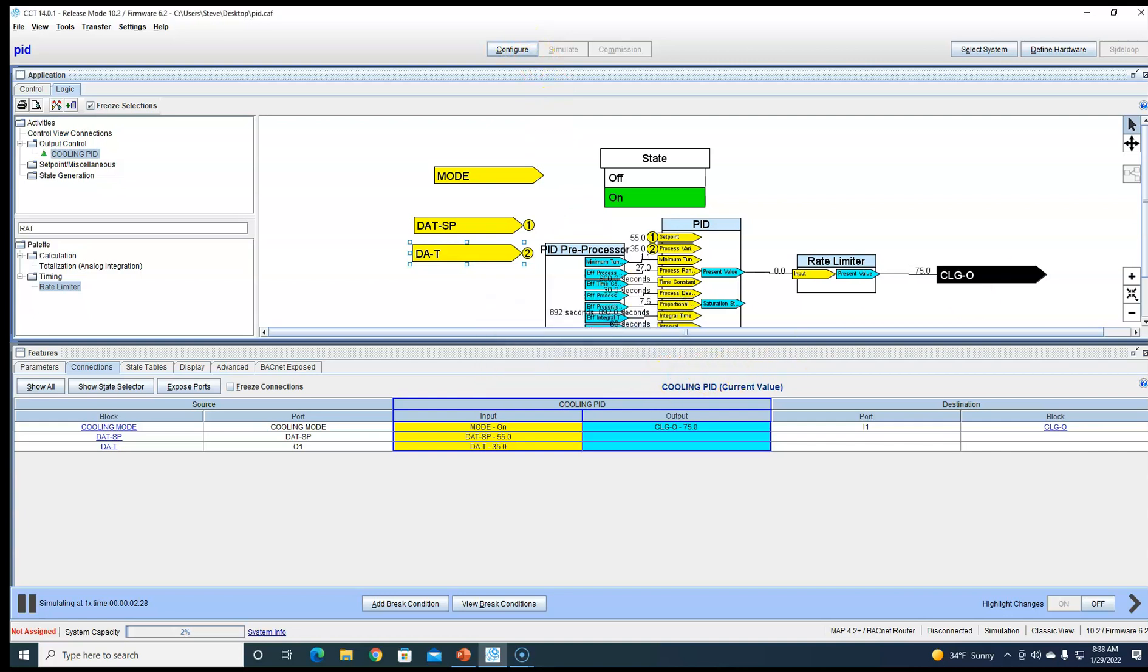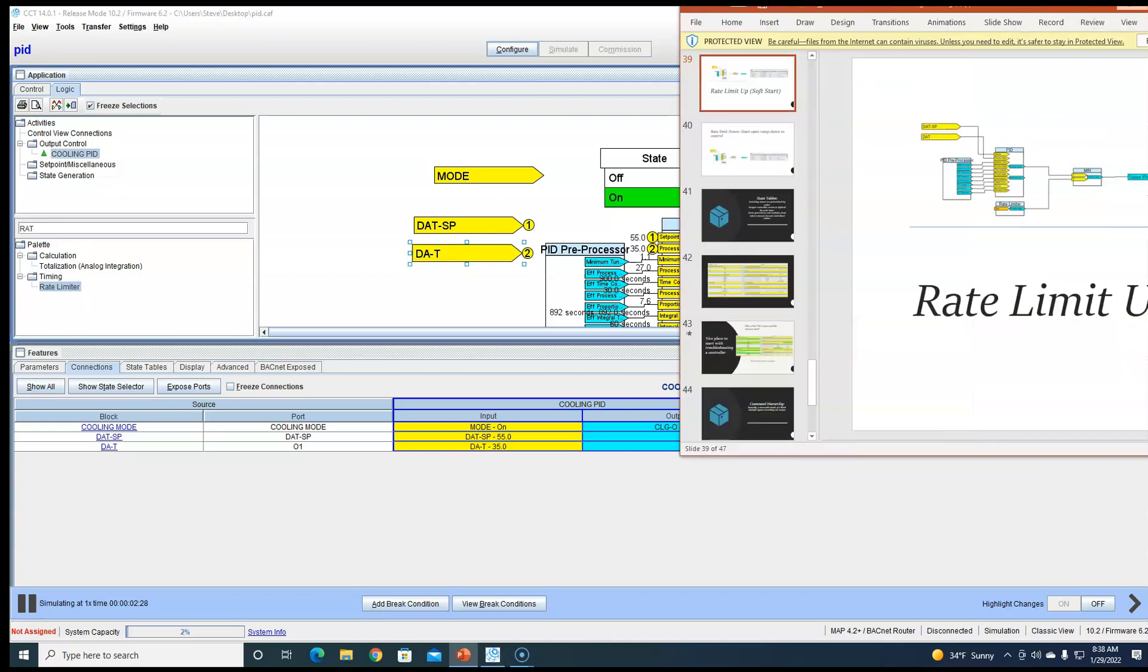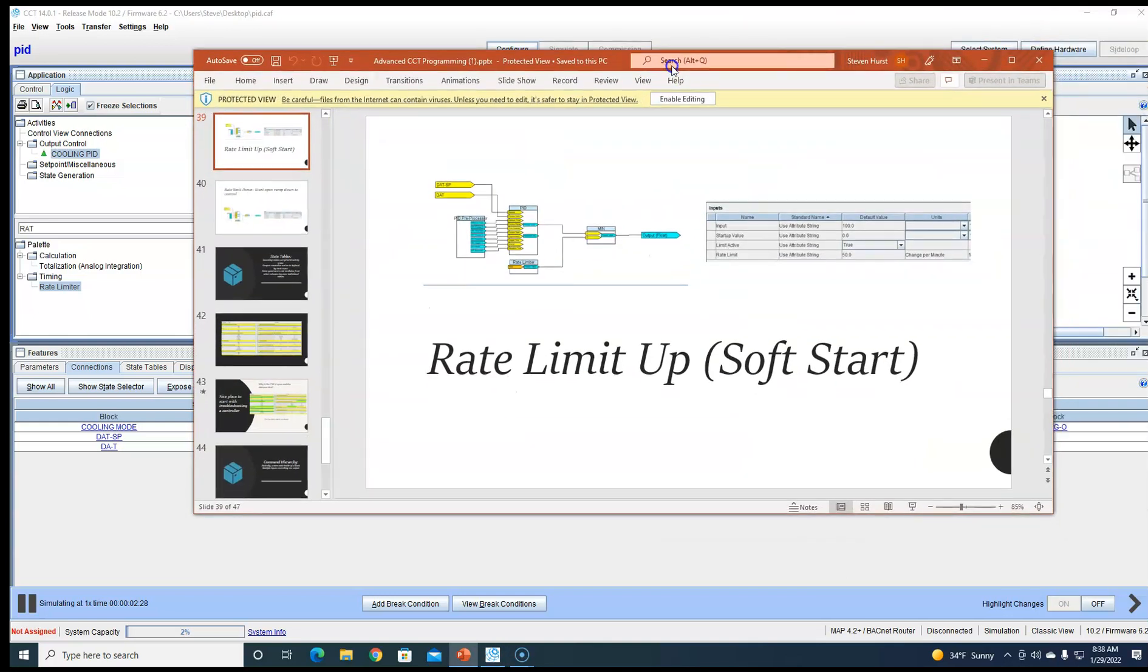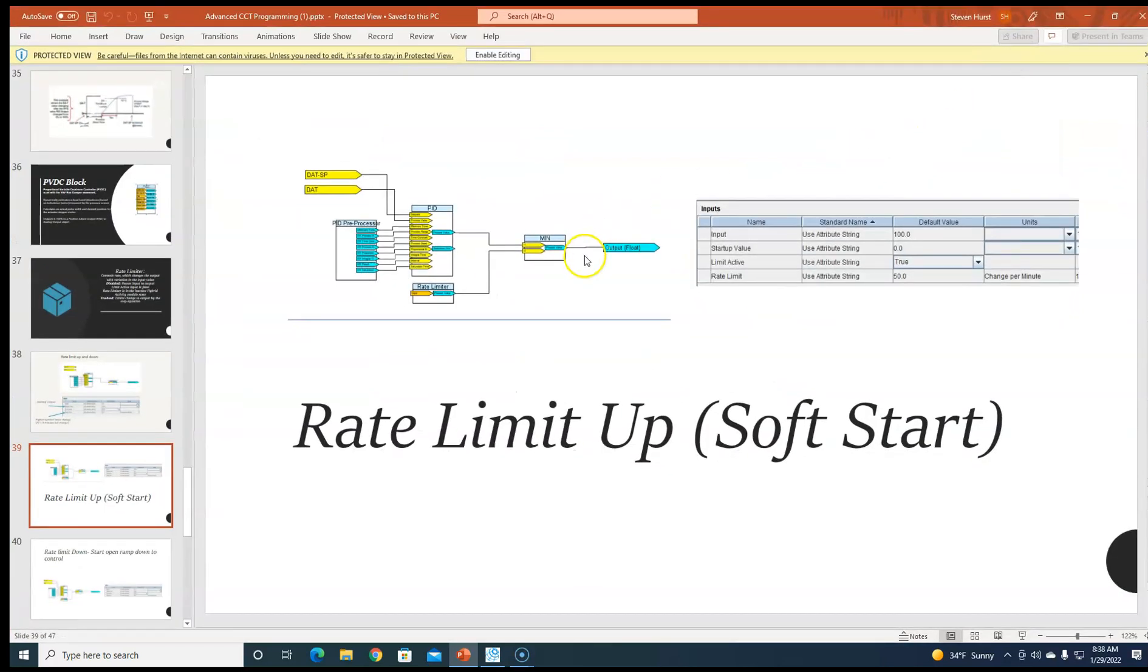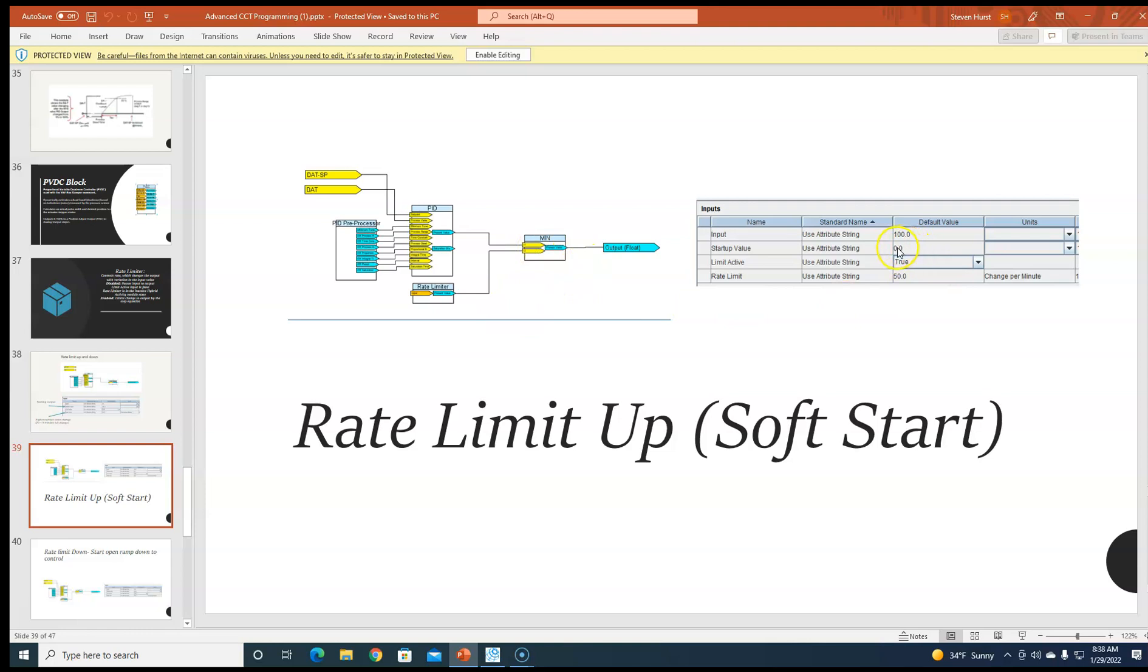Okay, what else can we do with the rate limiter? We can use it as a soft start. We can tie it to a min block with the PID coming in the top and the rate limiter coming at the bottom. We'll start the rate limiter at the startup value of zero, and then it'll take the min out of both of these and put it at the output. Why would you want to do this? Maybe your system's oversized or something like that. This will help out on that.